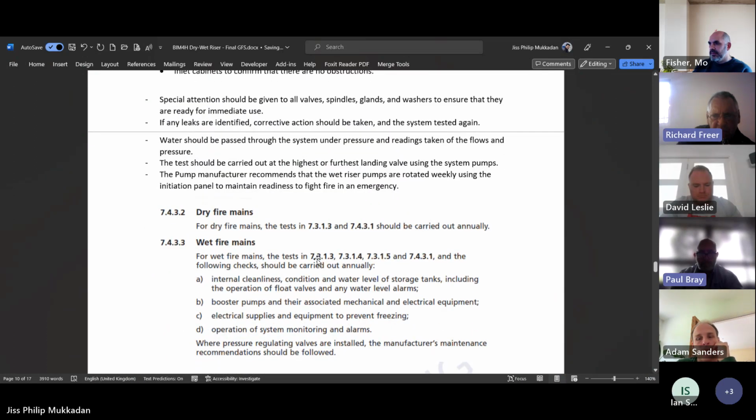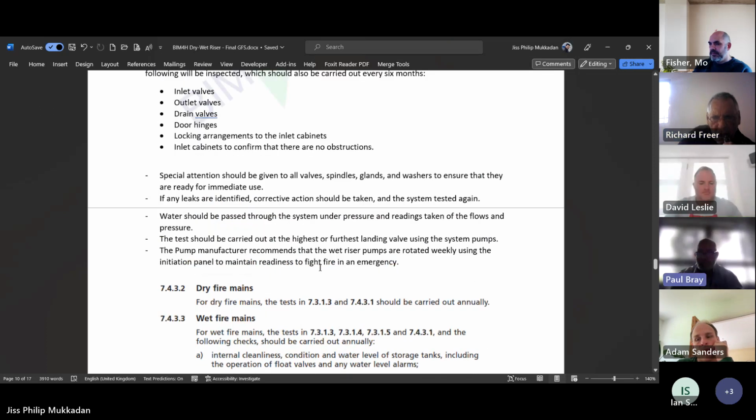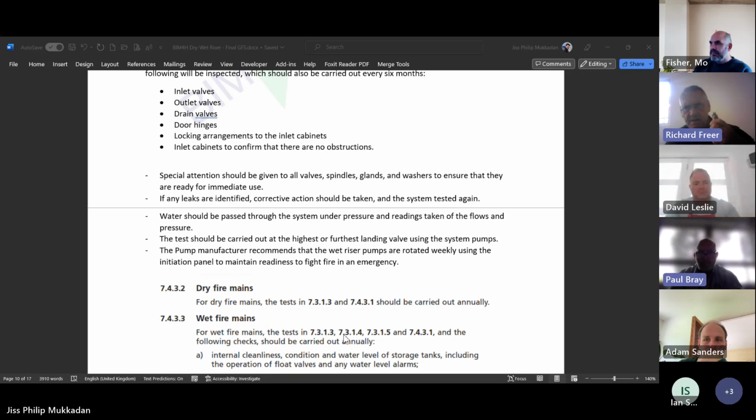So did somebody say this was Fire Safety England, what we're looking at now? Or did I misunderstand? The Fire Safety England regulations have just said that in buildings over 18 meters, there needs to be a monthly visual inspection. It's kind of like a non-technical inspection of all firefighting equipment, and they specifically put risers in there, but it's not hugely clear exactly what should be checked.